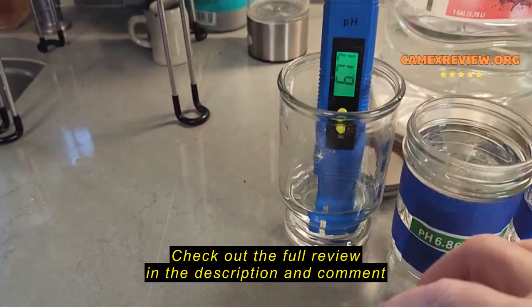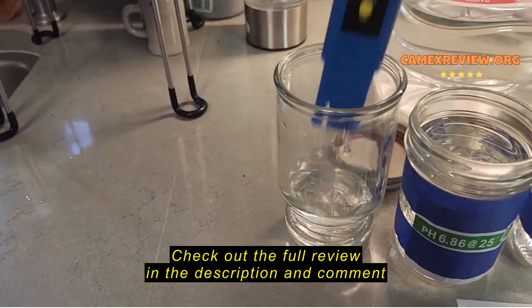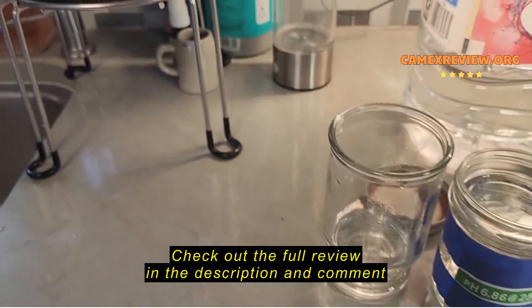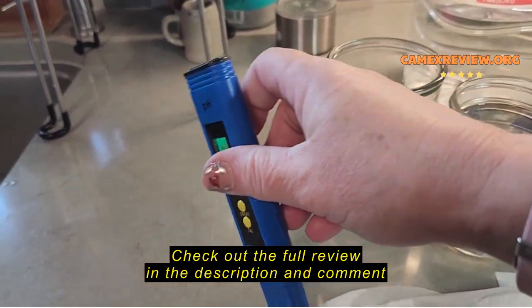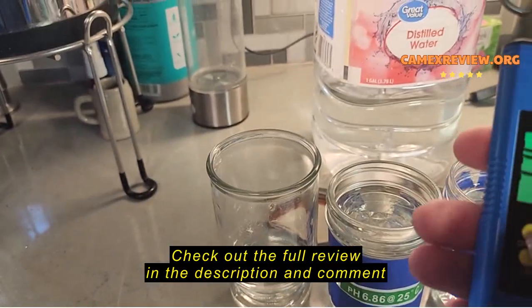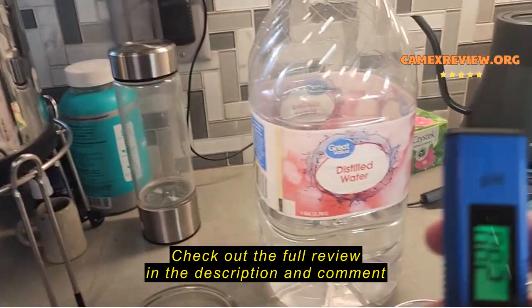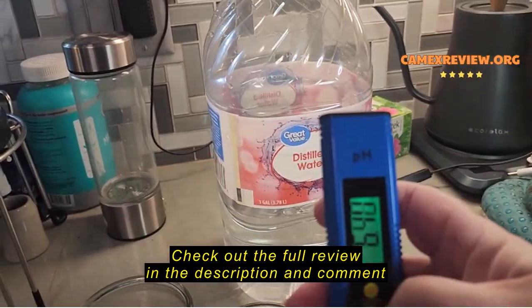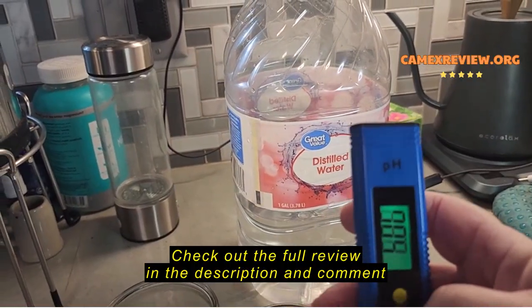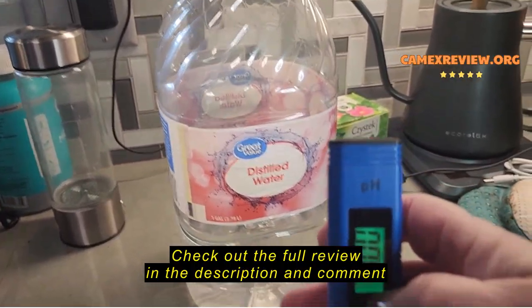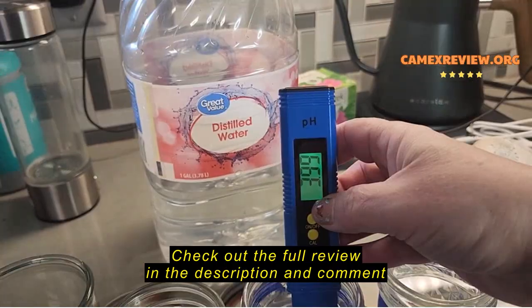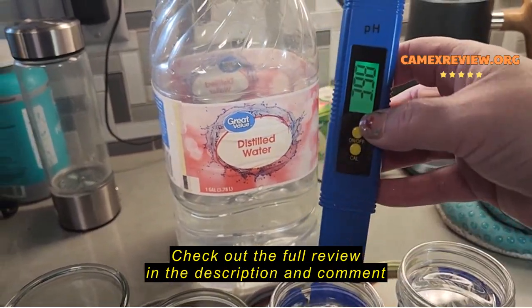Rinse it off again, dry it with the filter paper, and then you can go through each of the other 2. Again, hitting the calibration button for 5 seconds, but this time you hit it and now it's going to do the 4.0. And there it should be calibrated.